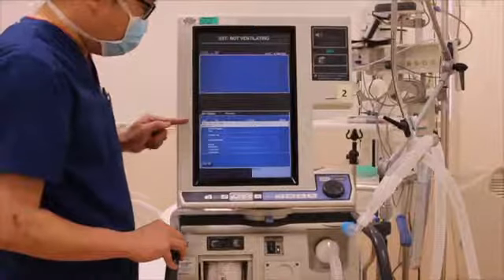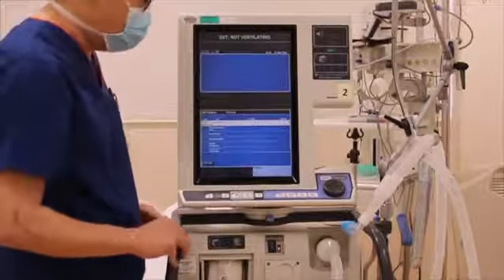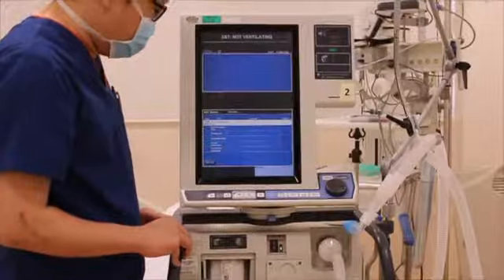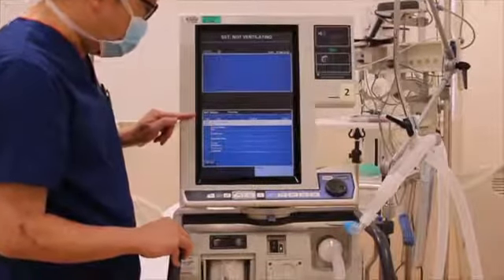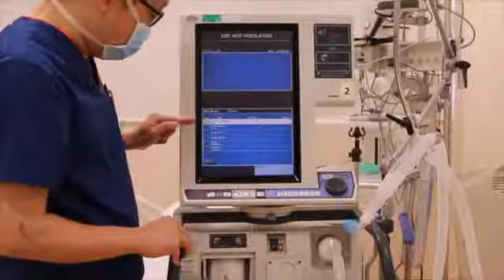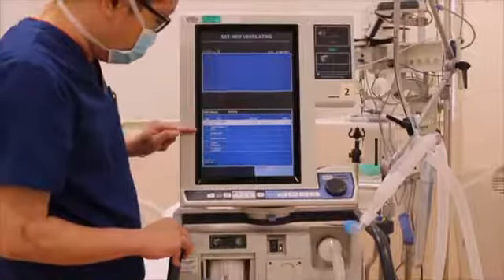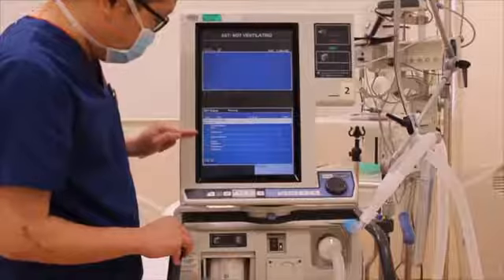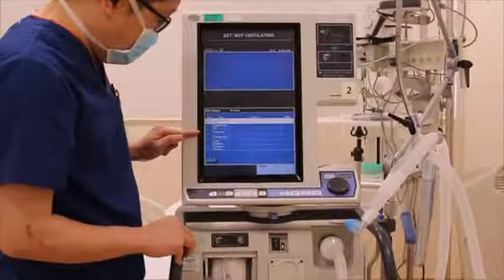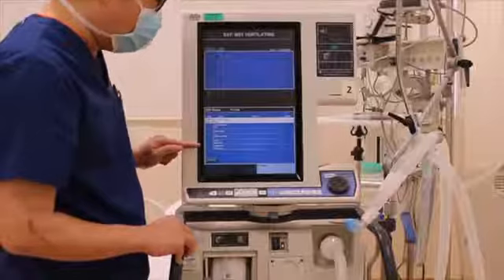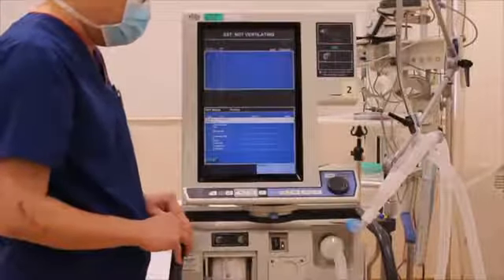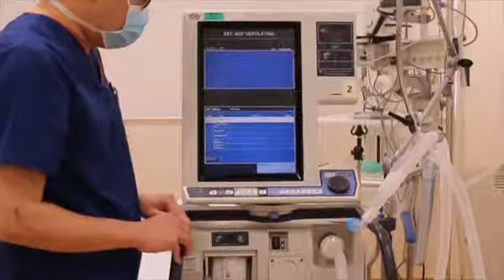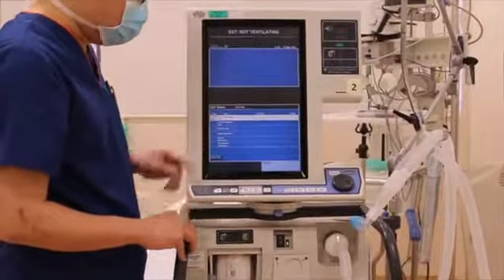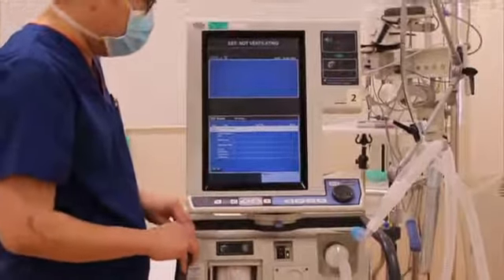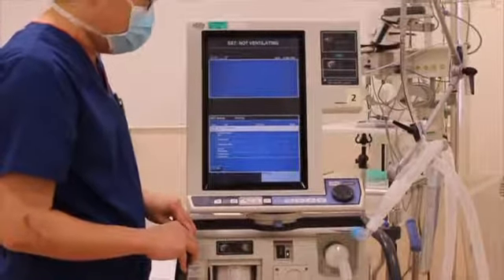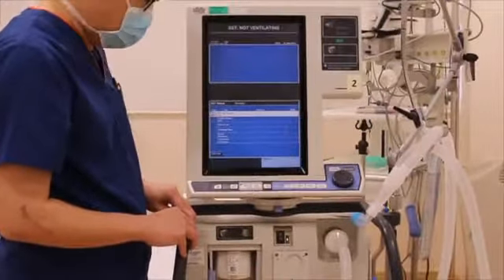The whole process of the SST will take about 5 minutes to complete. During this process, it will do multiple steps to check the sensor, the circuit pressure, presence of any circuit leak, checking the health status of the expiratory filter, as well as calibrating the circuit resistance and compliance in the last few stages. As the process continues, you will hear a lot of noise as well as pressure change occurring from the ventilator. This is the normal process, do not be alarmed.